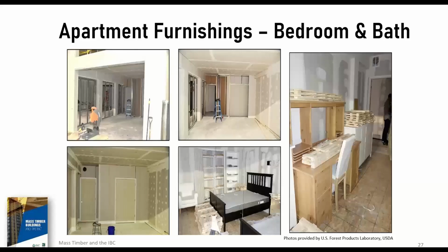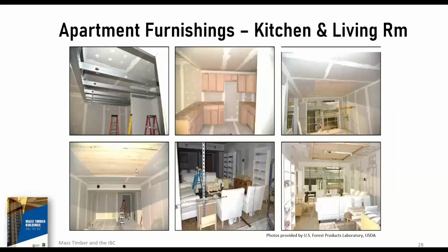It's about $5,000 worth of IKEA furniture up in flames. You can see in numerous locations, there's piled wood furring strips or blocking and cribbing used to increase the fuel load. They installed OSB sheathing on the floor to increase the fuel load as well. You can just see the cribbing is basically stacked everywhere. We have books on the shelf, the plastic coverings are still left on the mattresses, and you'll see those start to off-gas and pyrolyze during the fire tests.